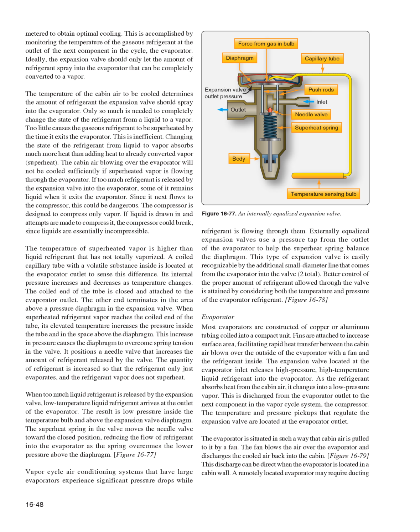If too much refrigerant is released by the expansion valve into the evaporator, some of it remains liquid when it exits the evaporator. Since it next flows to the compressor, this could be dangerous. The compressor is designed to compress only vapor. If liquid is drawn in and attempts are made to compress it, the compressor could break, since liquids are essentially incompressible. The temperature of superheated vapor is higher than liquid refrigerant that is not totally vaporized.